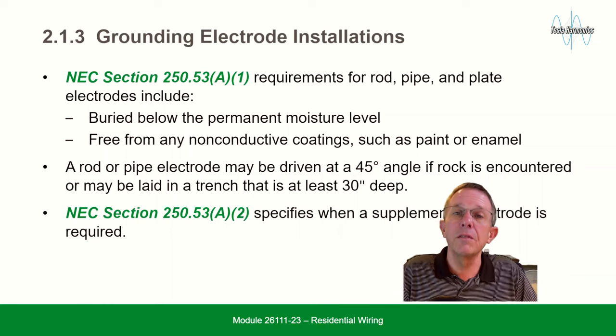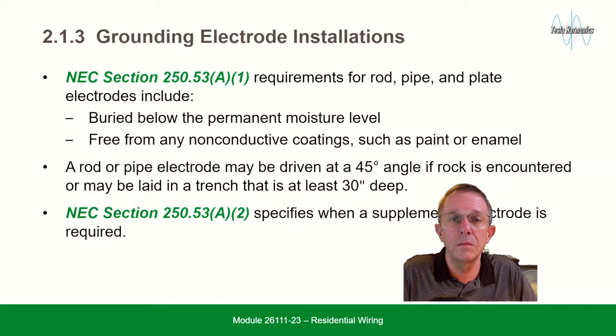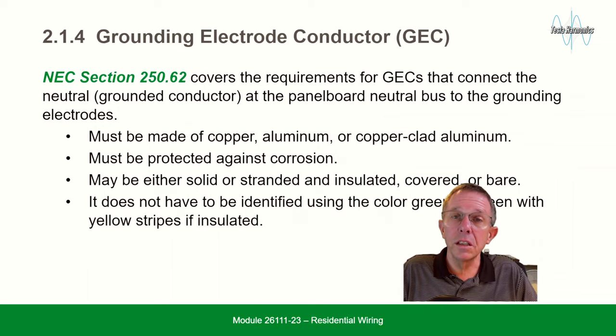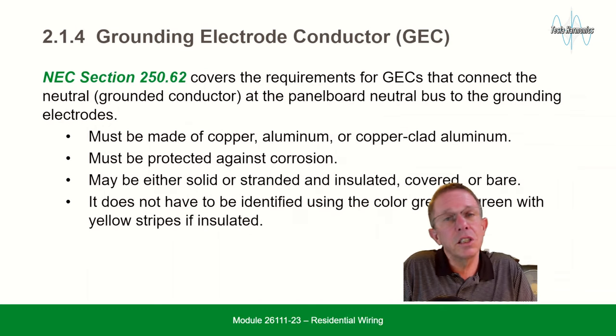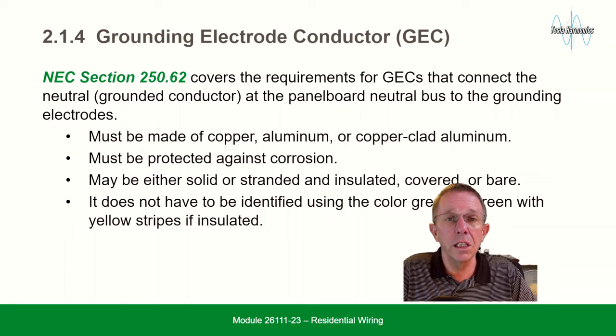NEC section 250.53 specifies when a supplemental electrode is required. The Grounding Electrode Conductor, or GEC: NEC section 250.62 covers the requirements for GECs that connect the neutral (grounded conductor) at the panelboard neutral bus to the grounding electrodes.